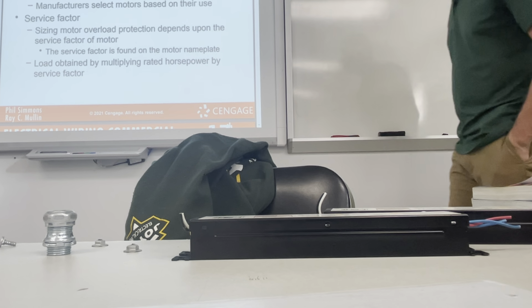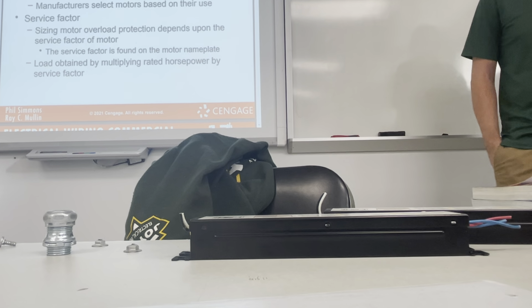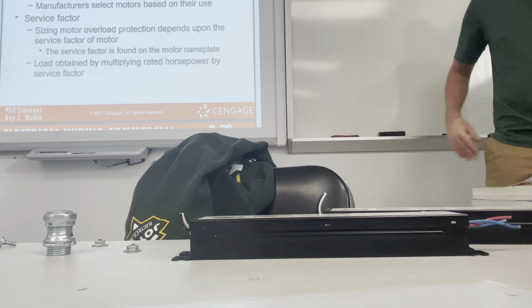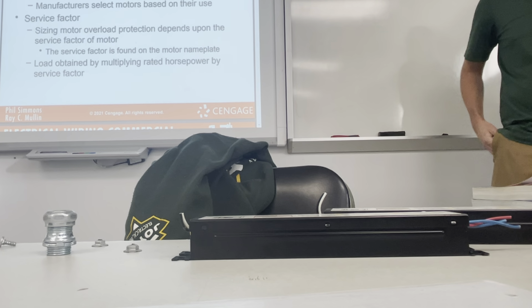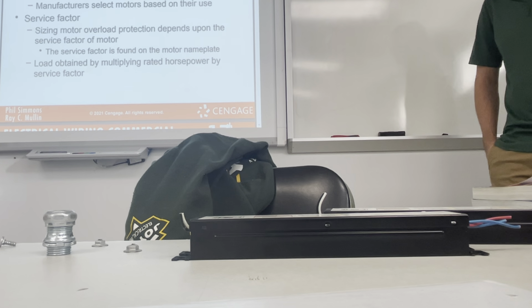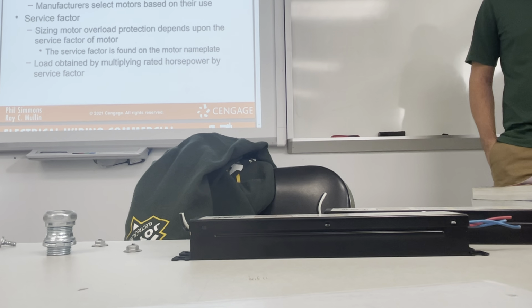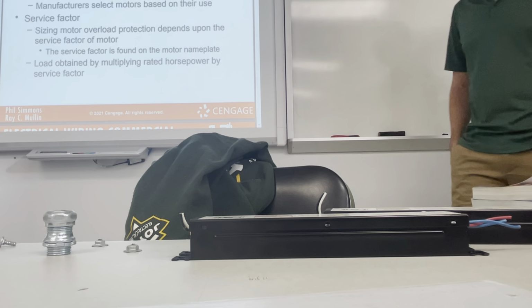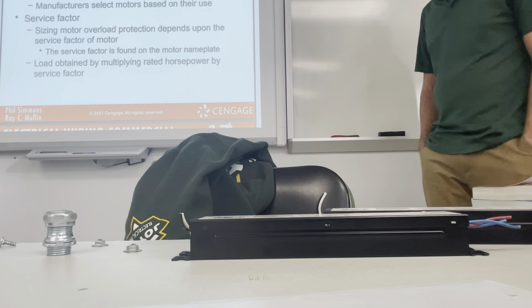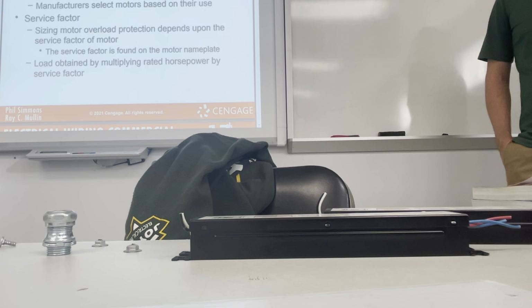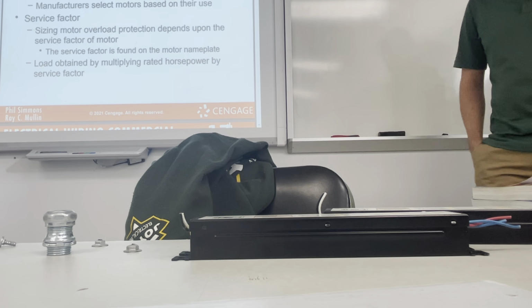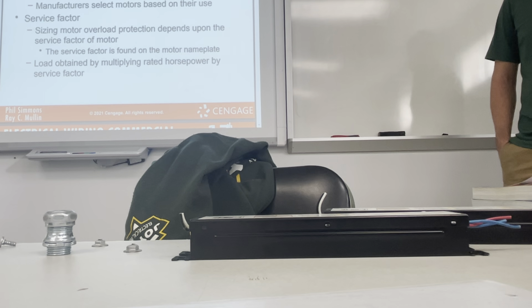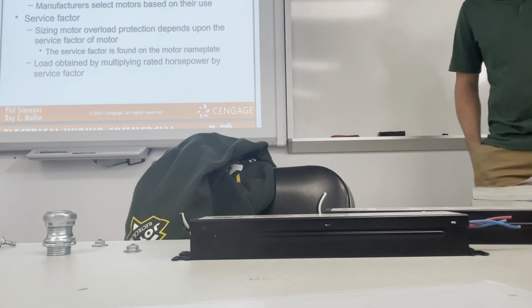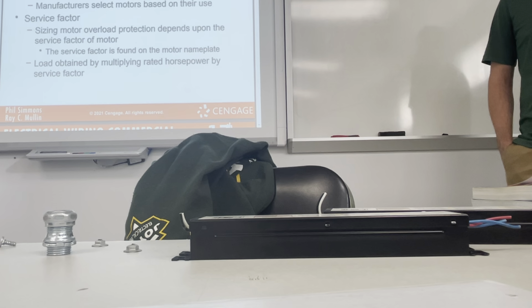Yeah, so there's always going to be a nameplate on your motor. And based on the motor, it might give you just basic information or it might give you a plethora of information. Usually the nicer the motors have more information. And more information for us is better because it leaves us less guesswork and less calculations to pull. They're usually going to tell you if it's rated for reverse, if it's rated for forward, if it's rated for slow speeds or just full speed. They'll give its insulation. It'll say what voltages it's rated for. It'll say its wiring pattern for those voltages. It'll give you pretty much everything on it.